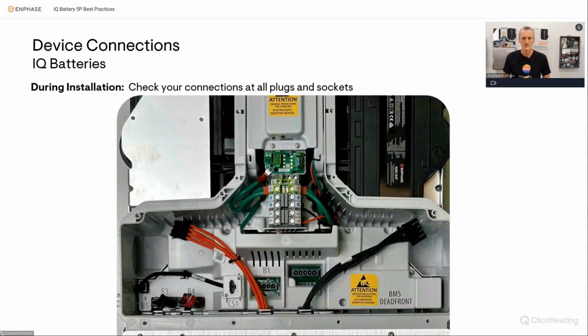During your installation, you want to check your connections at all the plugs and sockets. The first one, like on this IQ Battery 5 here, is that the DC connections into the battery are seated correctly. When microinverters in the IQ battery systems are shipped, they do not maintain a connection to the battery, so when you install a device, you must plug in the DC leads into the microinverter socket in the EES system to ensure the device can operate. That's a fairly obvious requirement, but you must ensure there's a click and a solid connection of the DC leads into the connection points.